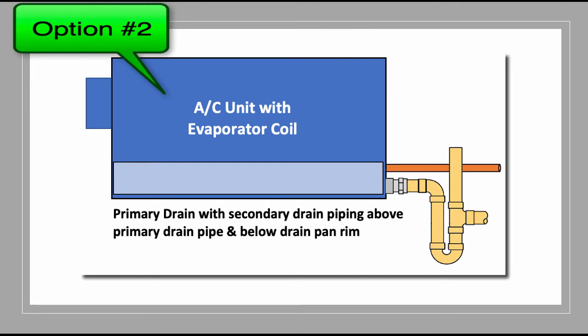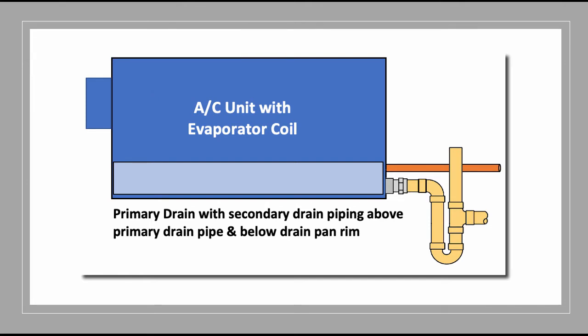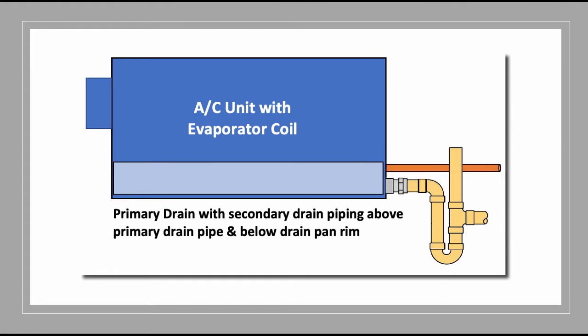Option two: you can use a secondary drain pipe on the primary drain, locating that secondary drain pipe above the primary drain location and below the lip of the top of the drain pan. Once again, you would locate that secondary drain piping to terminate in an observable location so that if the primary drain got clogged, it would indicate to the tenants of such condition.